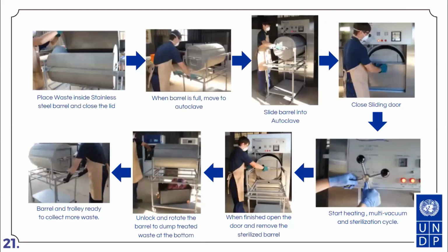This will be a typical layout or loading of a waste unit. So you'll start with placing your waste inside the stainless steel barrel at the top here, closing the lid, and once it is full, you'll move it to the autoclave. You'll close your sliding door, and once the door is closed, you'll start heating multiple vacuums and sterilization cycles.